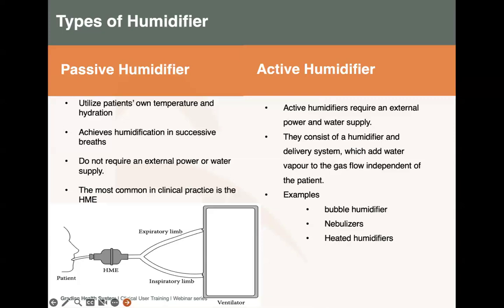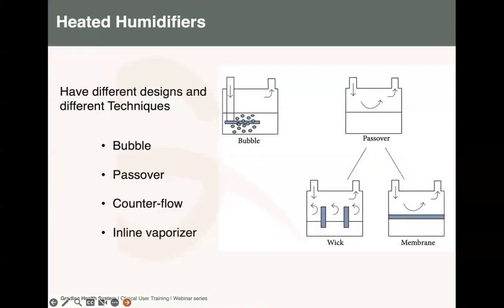Moving to the active humidifiers, these need an external power and water supply. They consist of a humidifier and a delivery system, which adds water vapor to the gas flow independent of the patient. Some examples of active humidifiers include bubble humidifiers, nebulizers, and heated humidifiers. Next slide, please, to see the different types of active humidifiers. We have the bubble humidifiers, the passover, which uses the wick and the membrane, the counterflow, and the inline vaporizers. All these are active humidifiers.